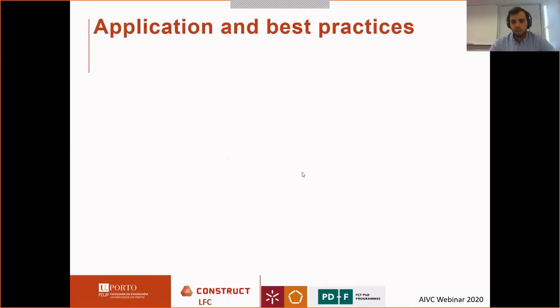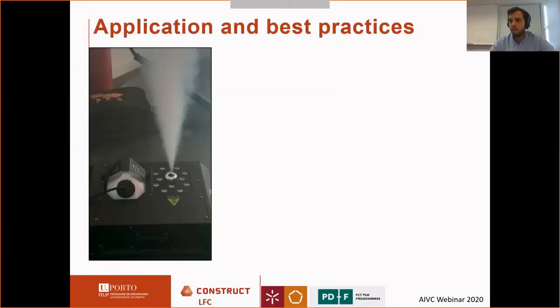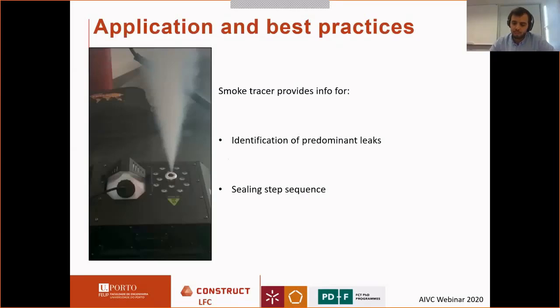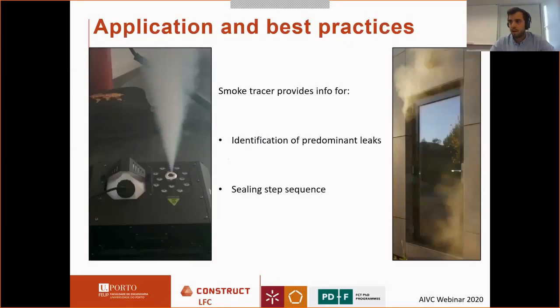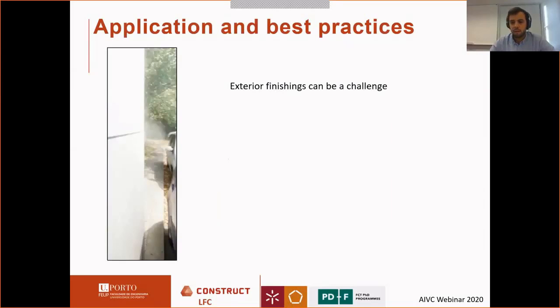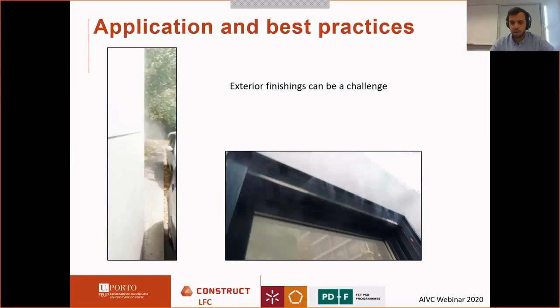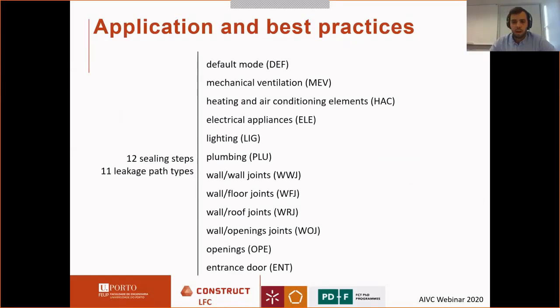For the application and best practices, a case study was assessed. We used a smoke tracer to identify predominant leaks and to establish the sealing step sequence. While some leaks were easy to identify, others were a challenge because of exterior finishings. After the initial assessment, 12 sealing steps and 11 leakage path types were selected, including mechanical ventilation, heating and air conditioning elements, plumbing, several types of joints, openings, and the entrance door due to its lower door gap.